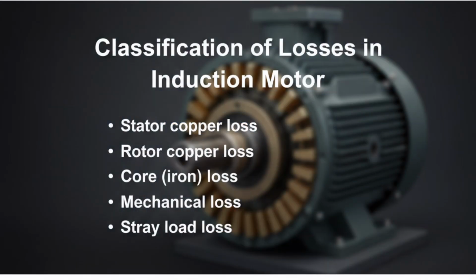Let us first understand the classification of losses inside an induction motor. Whenever electrical power is supplied to the stator, not all of it is converted into useful mechanical output at the shaft. Some power is lost in different parts of the motor. These losses include stator copper loss, rotor copper loss, core or iron loss, mechanical loss, and stray load loss. Electrical losses mainly arise in windings and magnetic core, while mechanical losses are due to rotation of moving parts. All these losses finally appear in the form of heat, raising the motor temperature.